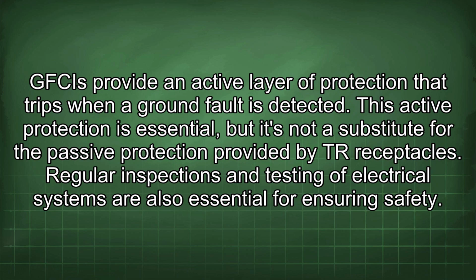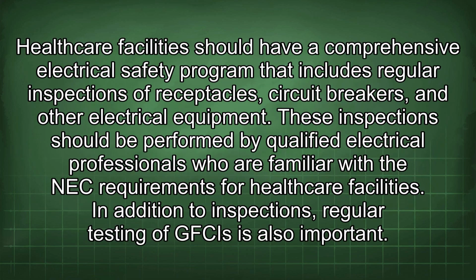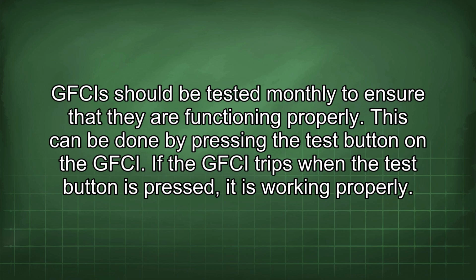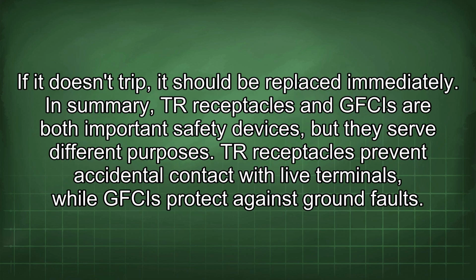Regular inspections and testing of electrical systems are also essential for ensuring safety. Healthcare facilities should have a comprehensive electrical safety program that includes regular inspections of receptacles, circuit breakers, and other electrical equipment. These inspections should be performed by qualified electrical professionals who are familiar with the NEC requirements for healthcare facilities. In addition to inspections, regular testing of GFCIs is also important. GFCIs should be tested monthly to ensure that they are functioning properly. This can be done by pressing the test button on the GFCI. If the GFCI trips when the test button is pressed, it is working properly. If it doesn't trip, it should be replaced immediately.